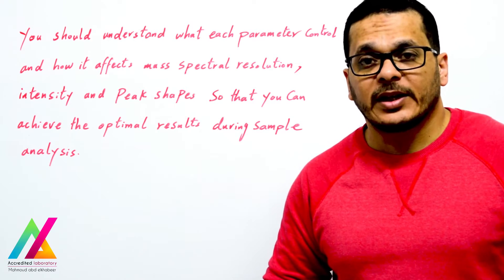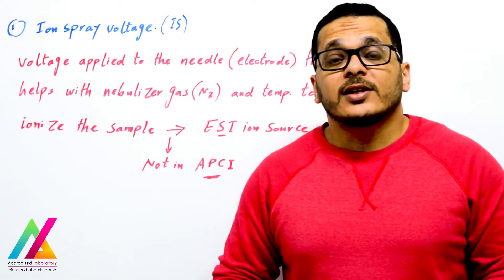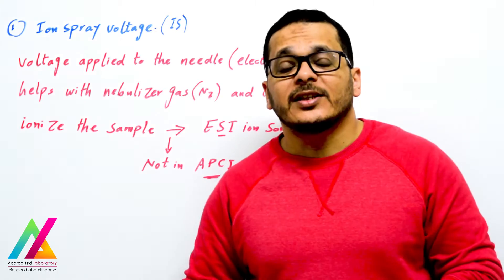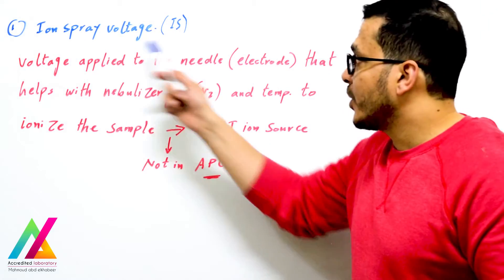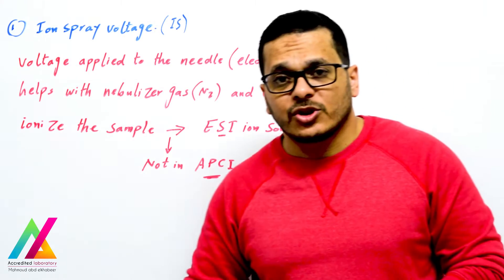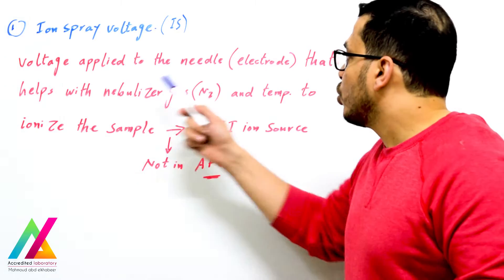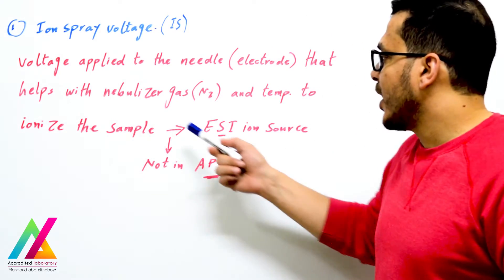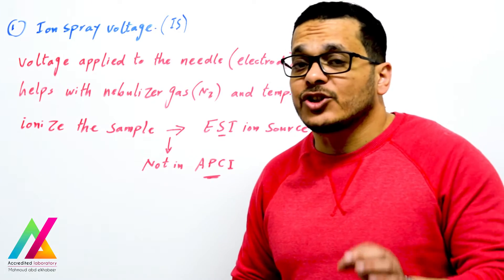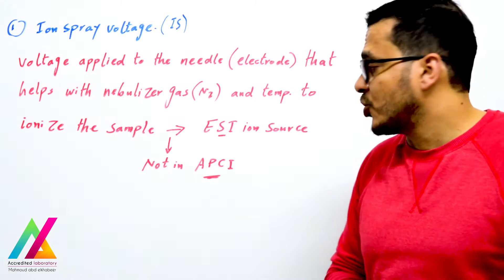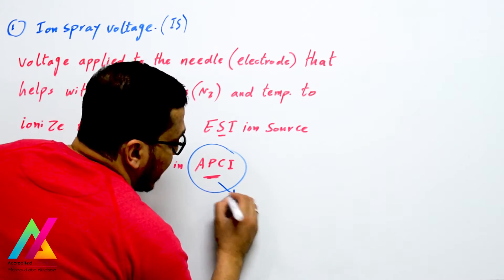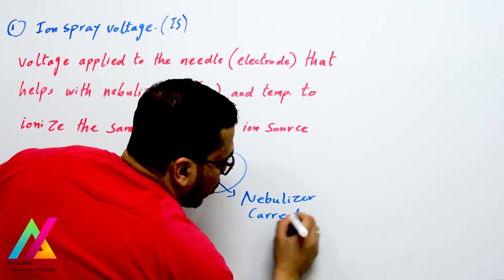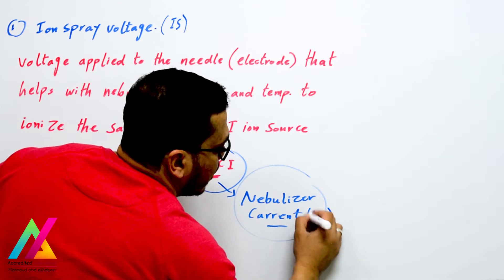The ion source is used for ionization of analyte molecules to produce ions, which are then transferred to the mass analyzer. For this process of ionization, we need nebulizer gas, temperature, and also ion spray voltage. Ion spray voltage is one parameter of your acquisition method — it is the voltage applied to the needle or electrode that helps the nebulizer gas and temperature to ionize sample molecules and produce ions. This applies in electrospray ionization; in atmospheric pressure chemical ionization, there is a nebulizer current applied to the corona discharge instead.